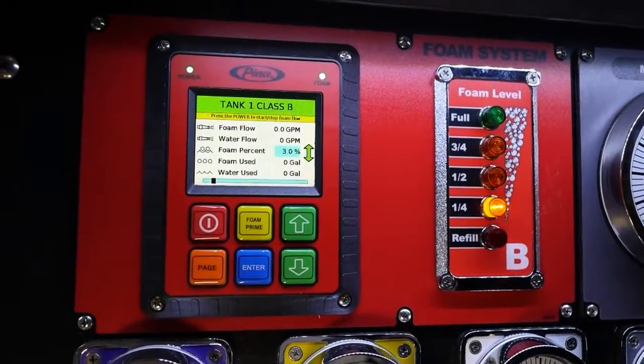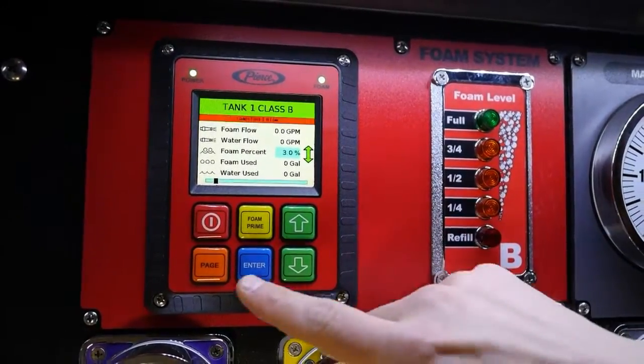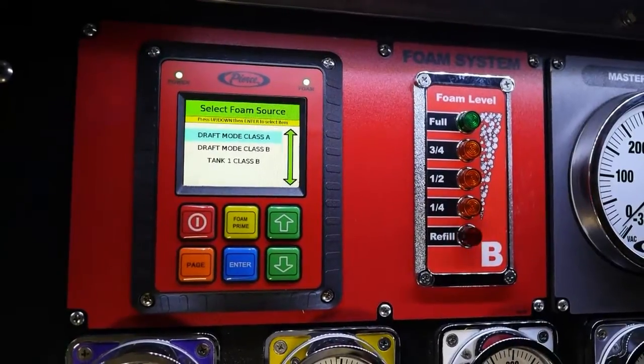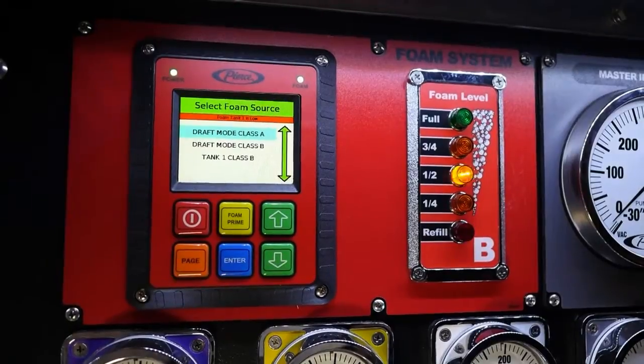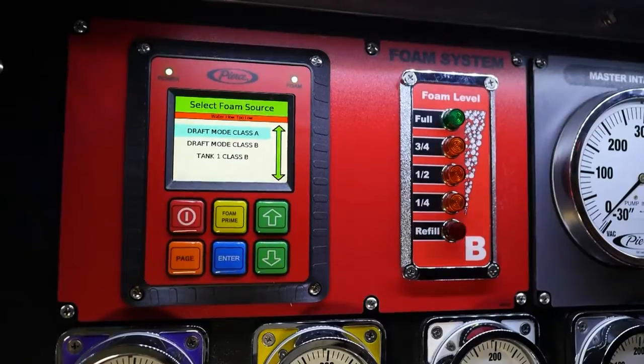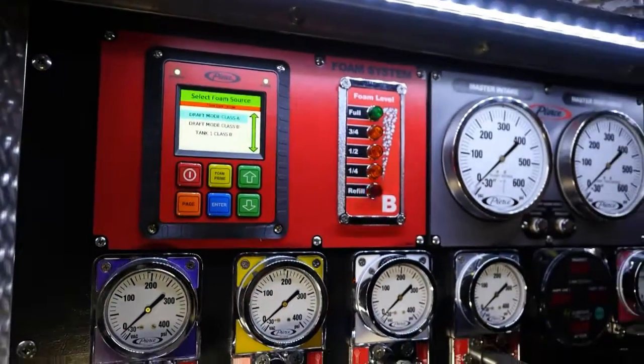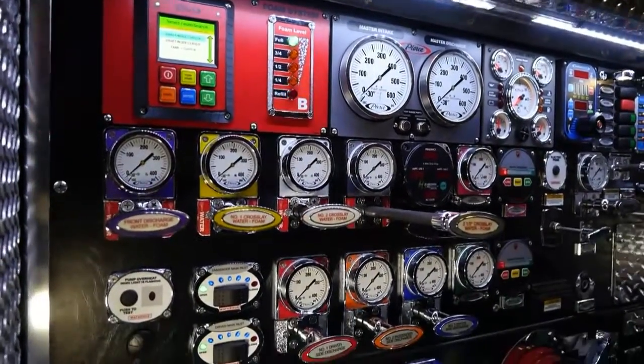In the event that you need to use foam other than the default foam for your apparatus, you simply touch the page button and go to the select foam source, which will then provide you a list of choices that are available, custom designed for your apparatus. A lot of these will toggle between different foam percentages like Class A and Class B. There is an integrated flush system on the Husky 12 that will automatically introduce a water stream between those two agents to prevent any type of coagulation of foam.